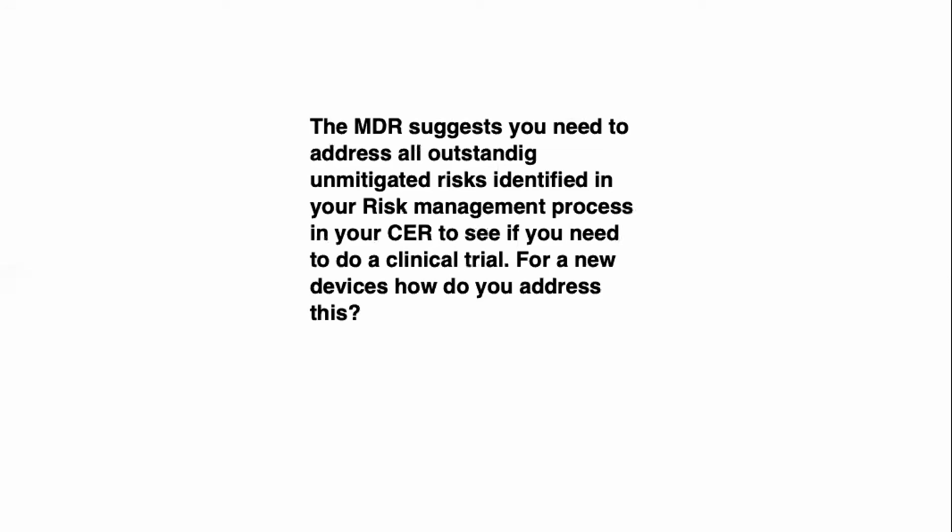If it's a new device in which you're using a predicate device as an equivalent comparator, you would then need to establish that the equivalent comparator, which is post-market, is a part of your risk management quality system, and that those unmitigated risks are identified and updated on an ongoing basis. So I hope that answered the question as best I can.